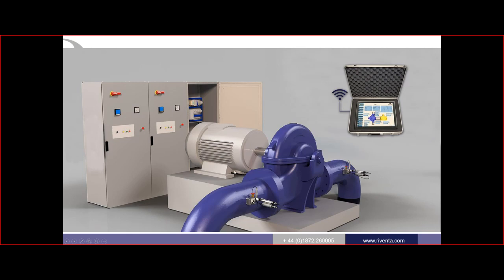So you can imagine here, you've got your sensors. In fact, you've got 10 pumps on this site. There's no trailing wires. You're straight into the 1/2 inch tapping point. So you're measuring, those two give you efficiency across that unit. This then goes back to a data station, which is basically a suitcase that's mains powered, that's used for setup, and it's got 4G, 3G communication.